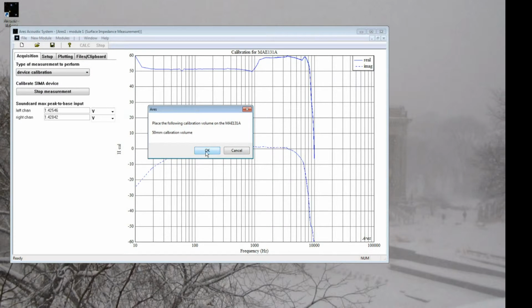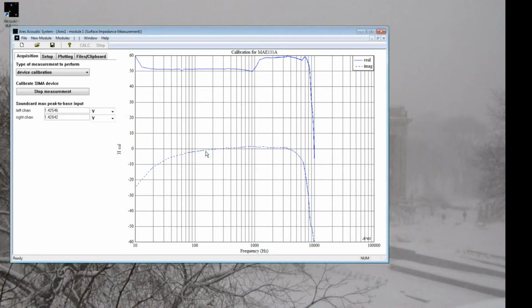So back at Ares, we'll go ahead and hit OK because we've put the calibration volume on. Now this might take a minute or so. Ares is going to run a sine sweep to do the measurement. First time it usually has to run it a couple times to get all the levels adjusted correctly. So you should hear a slow swept sine. Takes about 10 seconds to run, and it'll run a couple times. There it goes with the second run.